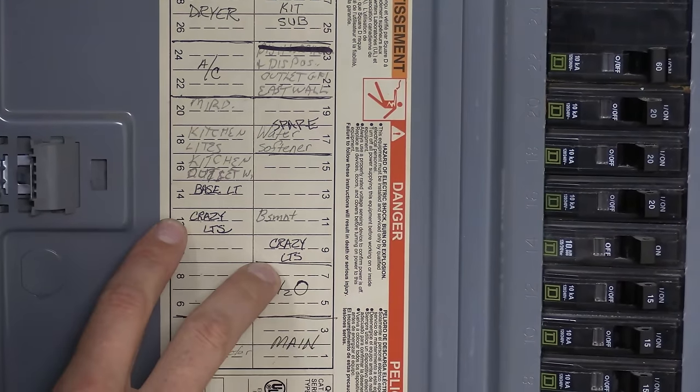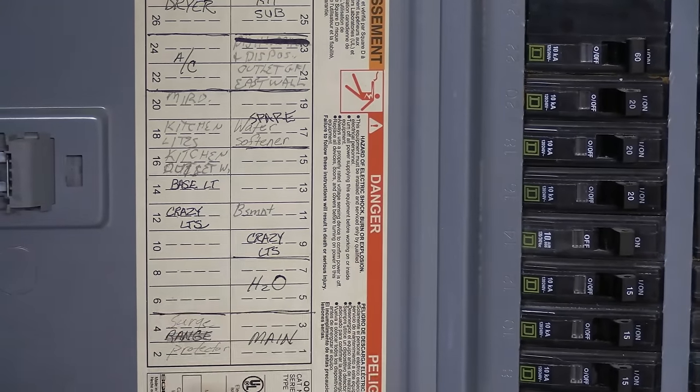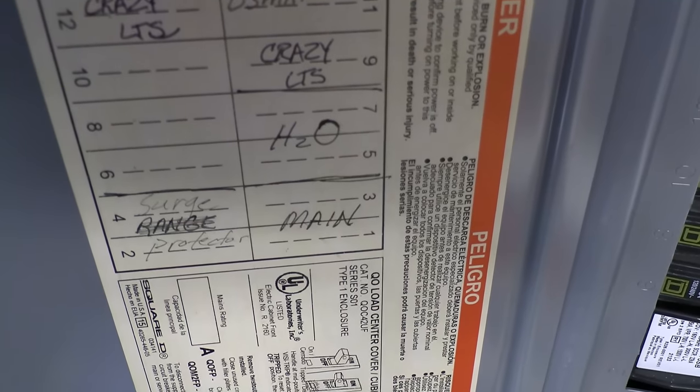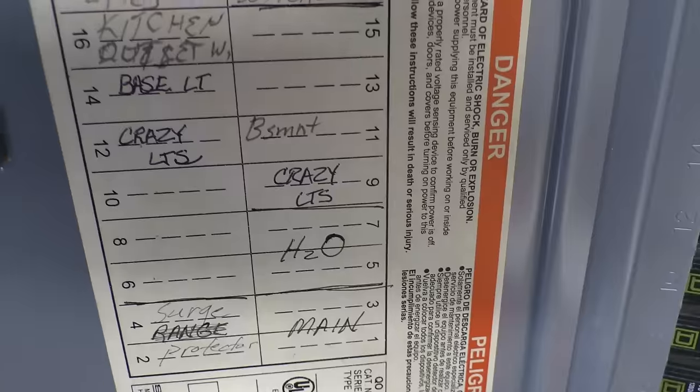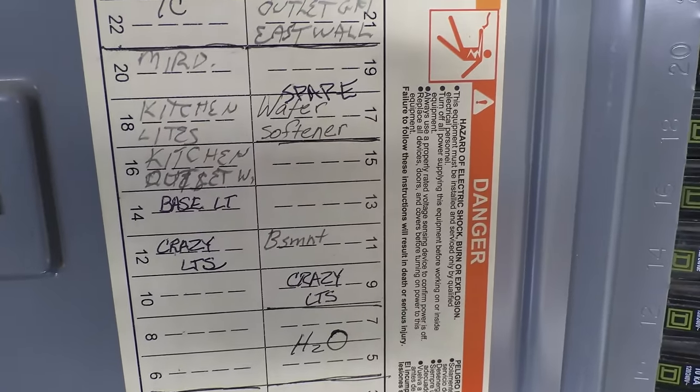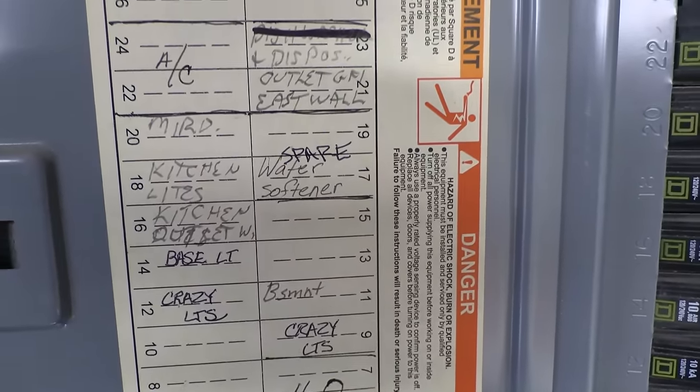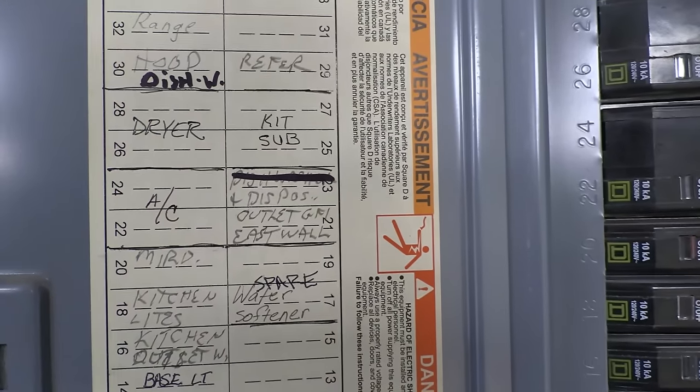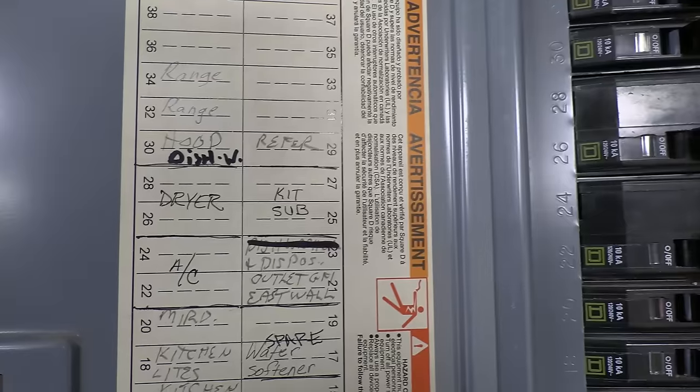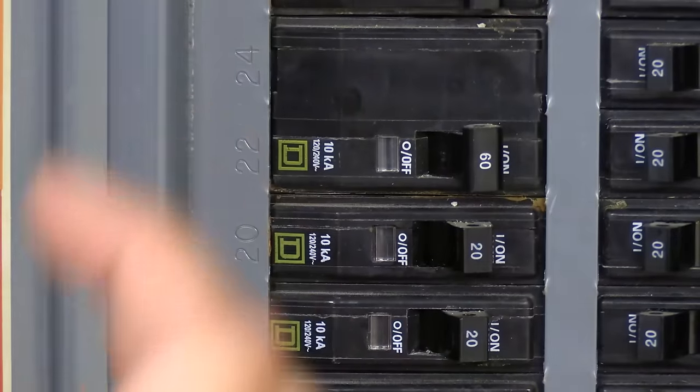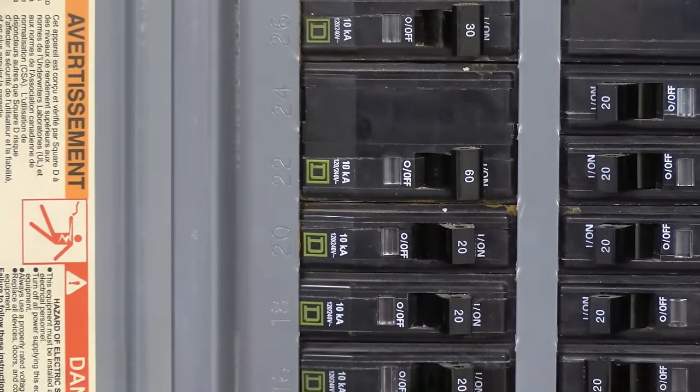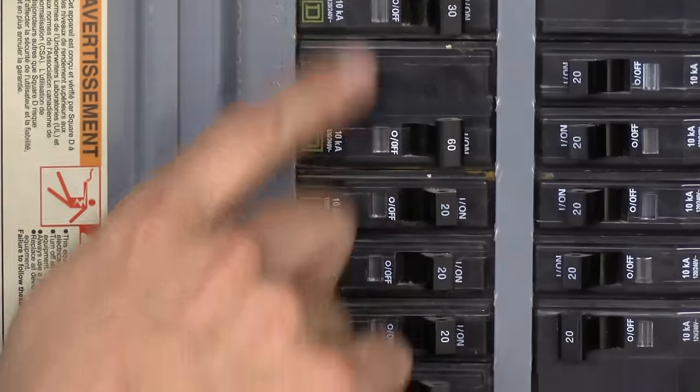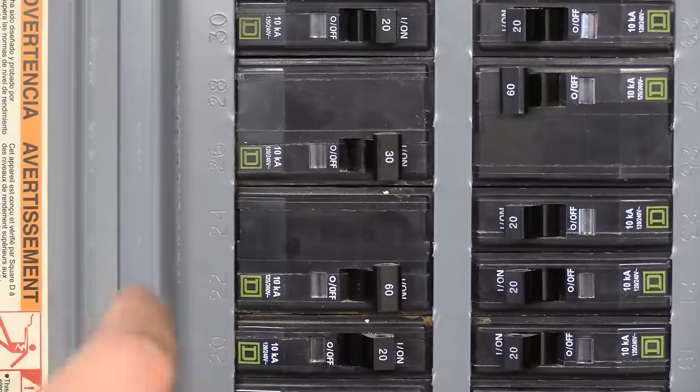So first, that's a code violation that each label must be distinct. And then secondly, crazy lights don't tell me if that's the behavior of the lights or maybe that's the dispersion of lights on that circuit throughout the house. It was too difficult to explain dining room, living room, bedroom, northeast bedroom, southwest bedroom. Functionally, the description couldn't be contained within the label. I'm wondering if that's what that means. Larger, physically larger air conditioners will often correlate to larger breaker sizes. Physically smaller air conditioners will often correlate to smaller breaker sizes.